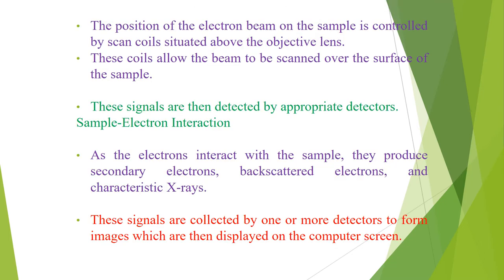The position of the electron beam on the sample is controlled by scan coils situated above the objective lens. These coils allow the beam to be scanned over the surface of the sample. As the name of the microscope suggests, this scanning enables information about a defined area on the sample to be collected as a result of the electron-sample interaction. A number of signals are produced and detected by the appropriate detector.